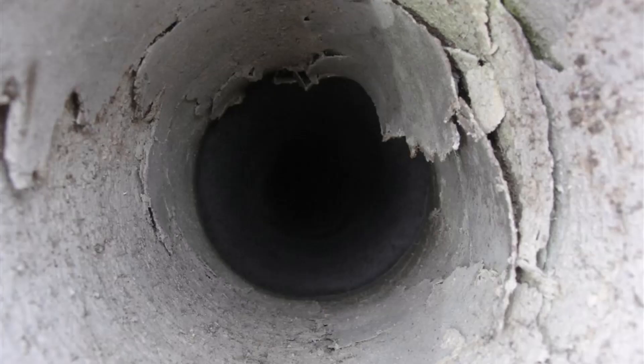The vent would go right up through the middle of the house and take the exhaust gases up and out, and it all worked well and good — until the stuff got wet. Once it got wet, either because you had condensation inside the flue because it didn't stay hot enough, or because you didn't have a good cover on top and rainwater got in, it would act kind of like a pastry where the inside would start collapsing in on itself in thin, paper-thin layers, eventually blocking the flue. That's the big concern, and I think that's why they stopped using them.